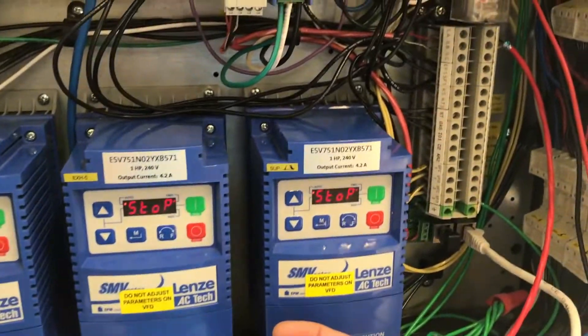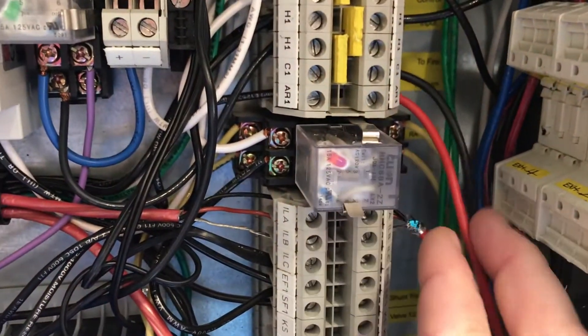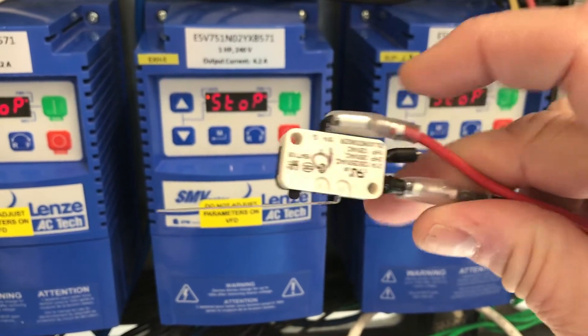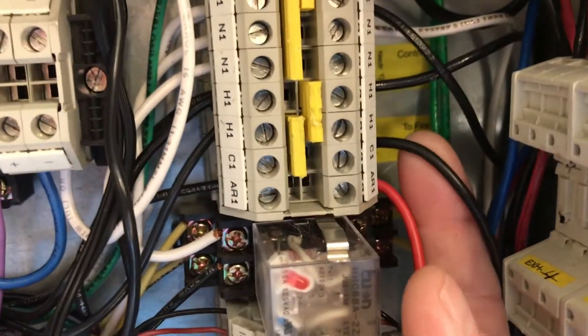This wiring configuration will make the hood package operate normally until the Ansul system is triggered, which will in turn operate the microswitch. Operating the switch will open the C1AR1 circuit and put the control package into fire mode. The last step is to restore all your power and to test the operation of the system.